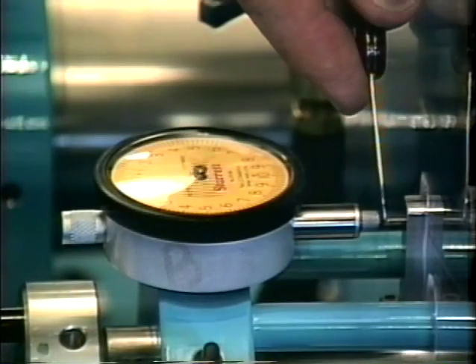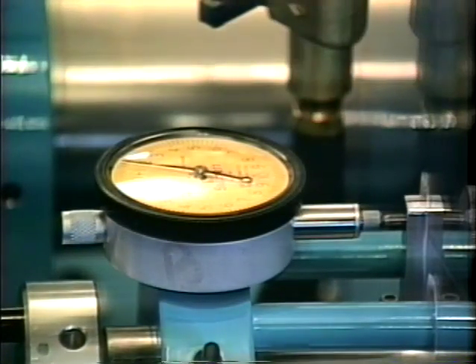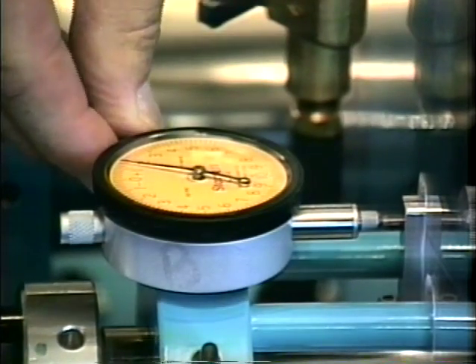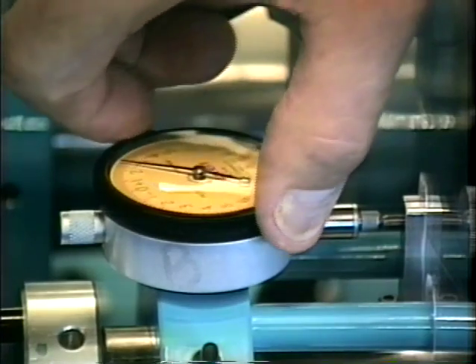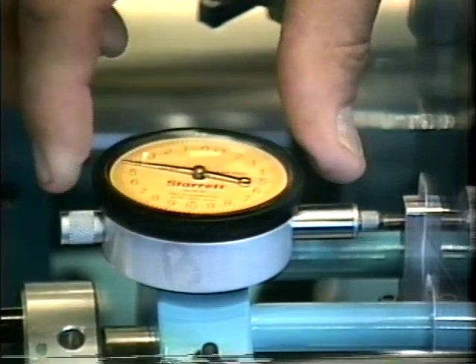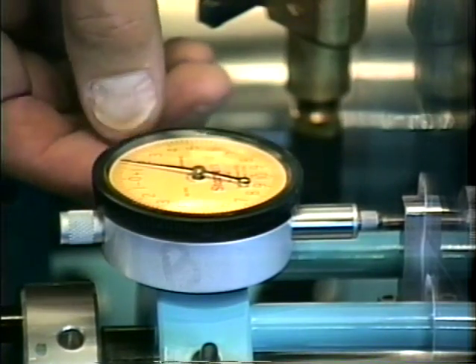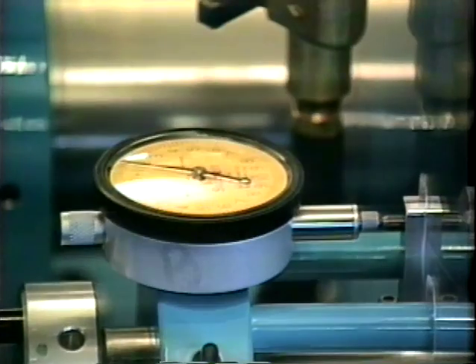sections. Here we're showing the amount of travel on the dial indicator rod, which by the way is only 20 thousandths of an inch. Another way to reference the dial indicator when calibrating it is to rotate the bezel. You notice the numbers on the dial plate are following the bezel when it's rotated. Once you have it set, lock it with the knob.